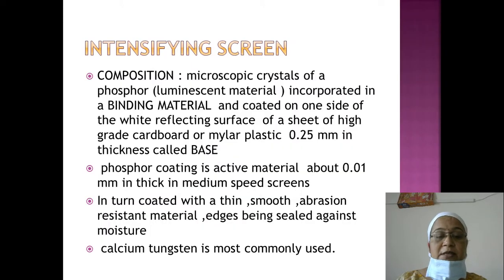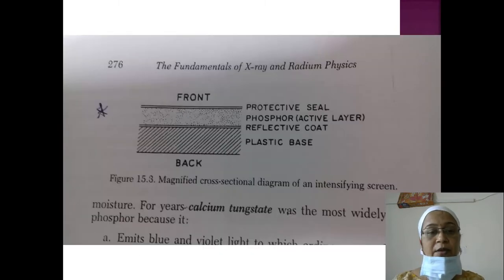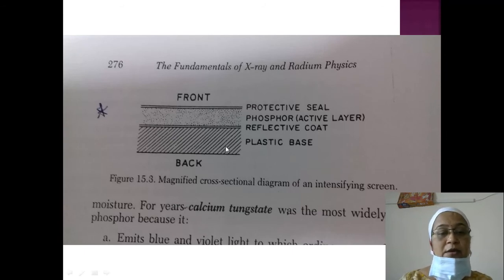The active layer is coated with a thin, smooth, abrasion-resistant material and its edges are sealed against moisture. Calcium tungstate is the most commonly used phosphor. The important point to remember is that the screen contains microscopic crystals of phosphor coated over a base sheet of high-grade cardboard or mylar plastic. The cross-section of the screen shows the back, the active phosphor layer, the reflective layer, and the protective seal.